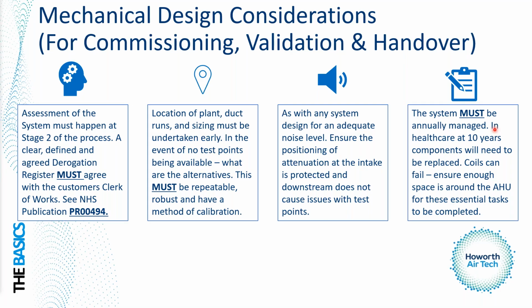I validated air handling units where the fog coil on the front of the air handling unit wouldn't come out. It was stuck in between a riser and another air handling unit, and that system was accepted. But that should have been picked up early and adequately assessed through the derogation or whatever it might have been. But there was no process in place to get that out if it was to burst.